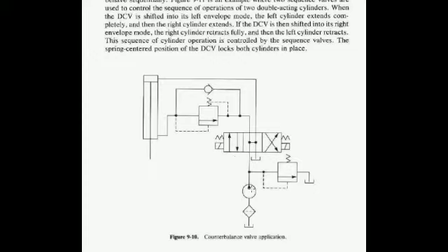flow, whatever the pump flow that is coming, will flow in this manner and circulate to the A port, in this direction. But here we are having the blocked condition, and here we are having a one-way check valve. If the pressure is more than the spring force of this check valve, then obviously the fluid will flow in this manner and come to the blind end of the cylinder. So we will get the vertical motion of this cylinder.